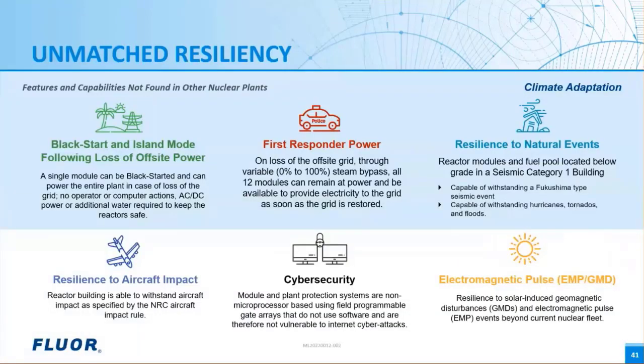I mentioned the resilience of this reactor. The resilience is driven by several different features. I'll start first with some of the features in NuScale that aren't found in other plants. One is black start or in the island mode. Typically, when a nuclear power station loses the offsite grid, there's no outlet for the power, and the reactors are tripped and go offline and shut down.